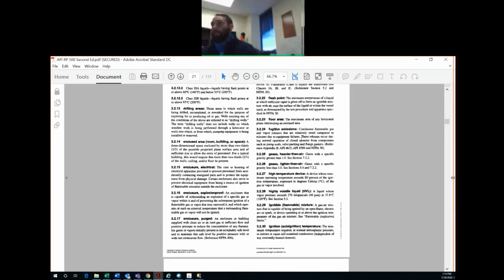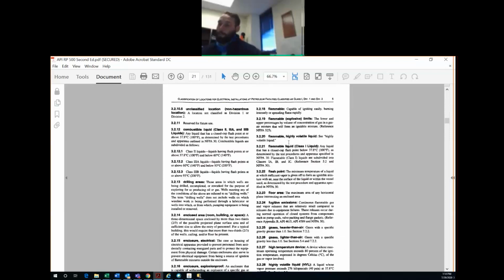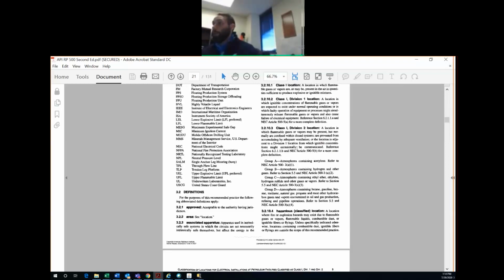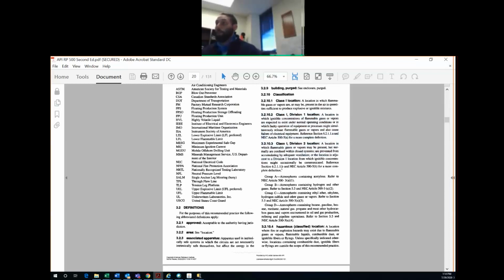Okay, obviously all these definitions are important, but in this class, we're whittled down to an hour, so we're going to try to cover the most important ones. And the most important I can think of is what is the definition for Class 1 Div 1 and Class 1 Div 2. So a Class 1 Div 1 location, I'll just read this verbatim, a location in which ignitable concentrations of gas are expected to exist under normal operating conditions, or in which faulty operation of equipment or process might simultaneously release flammable gases or vapors and also cause the failure of electrical equipment.